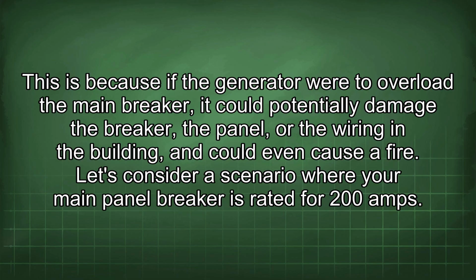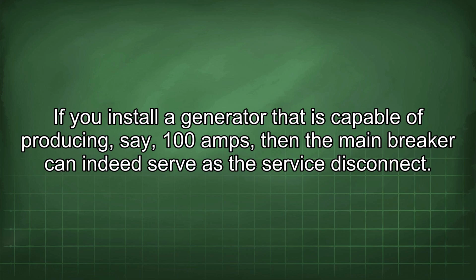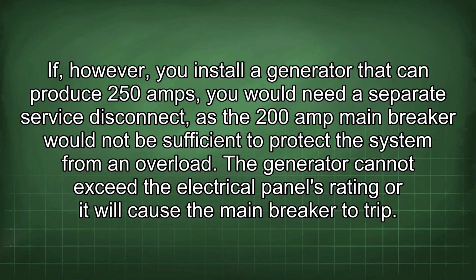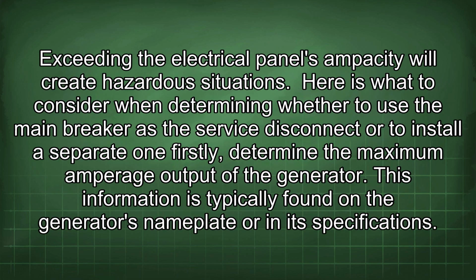Let's consider a scenario where your main panel breaker is rated for 200 amps. If you install a generator that is capable of producing, say, 100 amps, then the main breaker can indeed serve as the service disconnect. If, however, you install a generator that can produce 250 amps, you would need a separate service disconnect, as the 200 amp main breaker would not be sufficient to protect the system from an overload. The generator cannot exceed the electrical panel's rating or it will cause the main breaker to trip. Exceeding the electrical panel's ampacity will create hazardous situations.